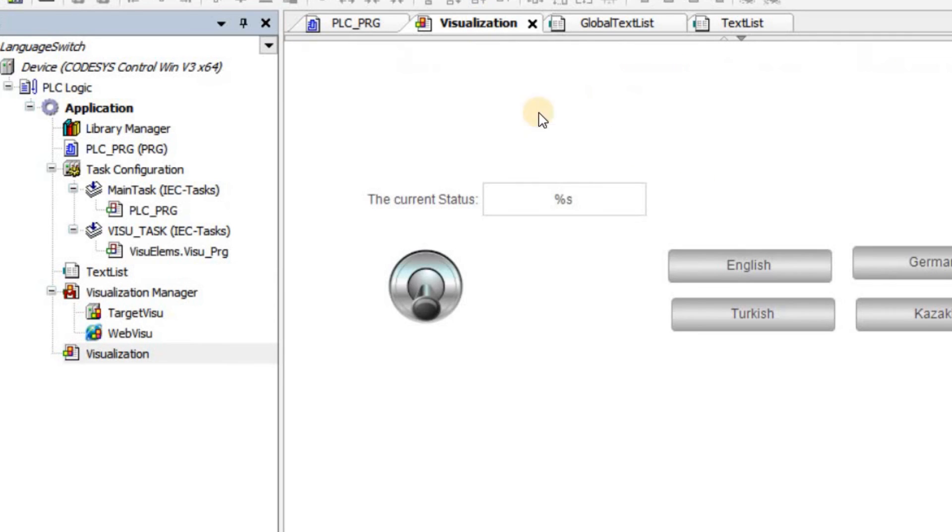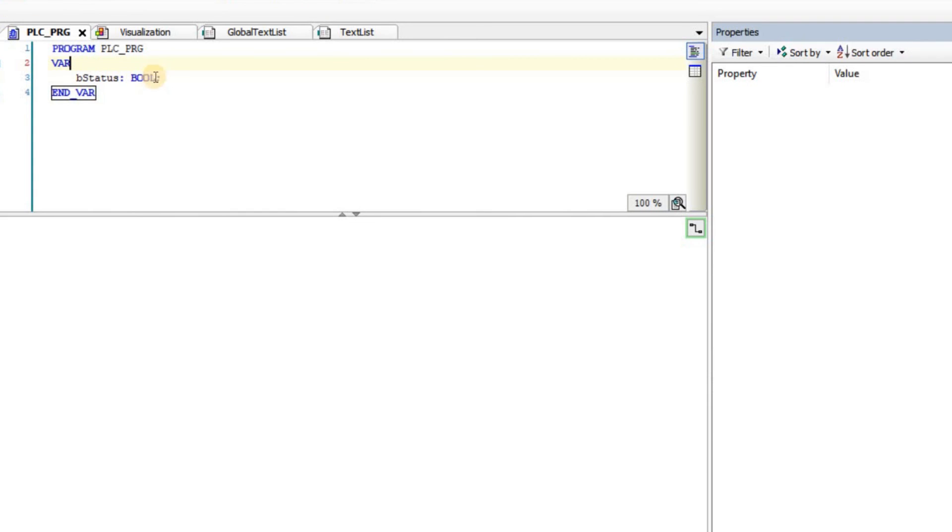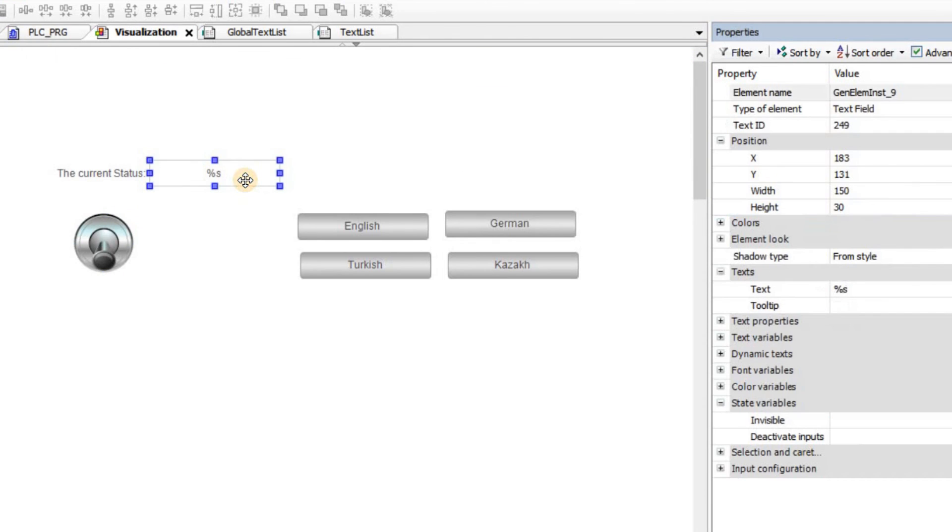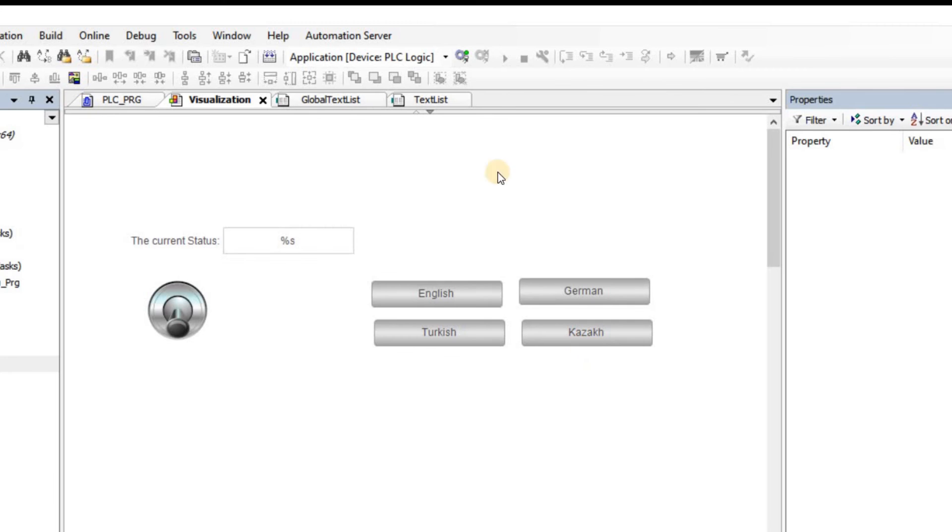Also in the visualization, I have inserted a switch. I have associated it with a new variable that I have declared in the PLC_PRG as B_status, a boolean variable that you can see here. And also for my text field, I have determined the text list as the one that I have just created and shown you. And also for the index, I've used the same boolean variable.